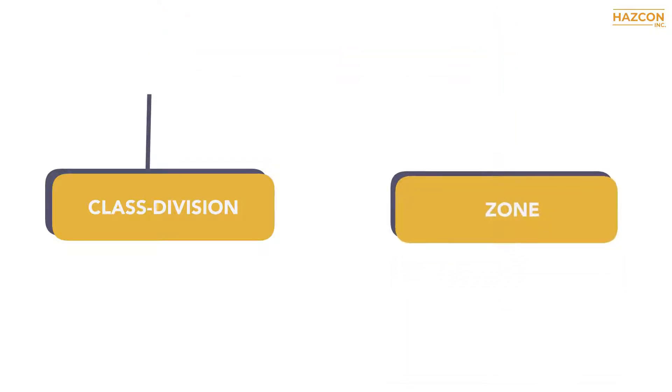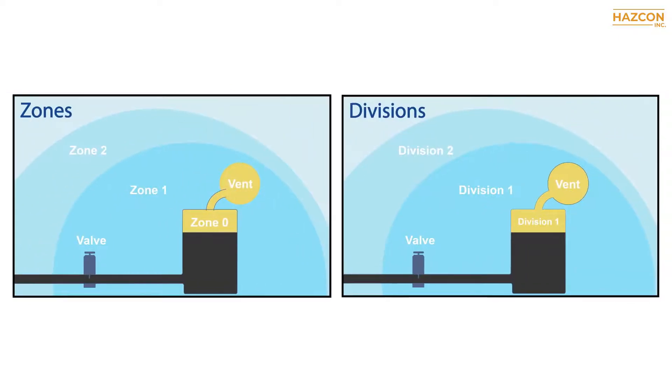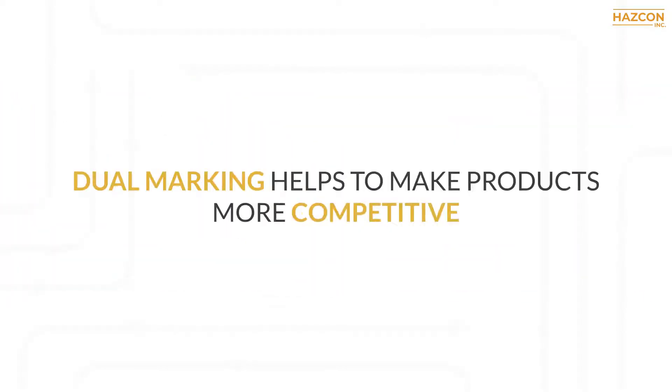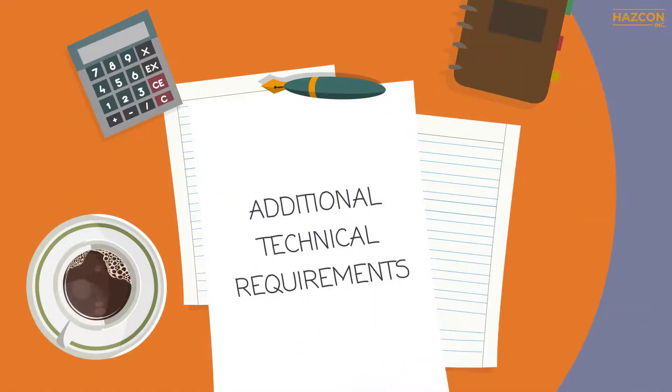Some products have dual markings with both class division and zone markings so that the product may be installed in both division and zone hazardous areas in North America. Dual marking helps to make products more competitive, but there are additional technical requirements and rules and procedures to follow.